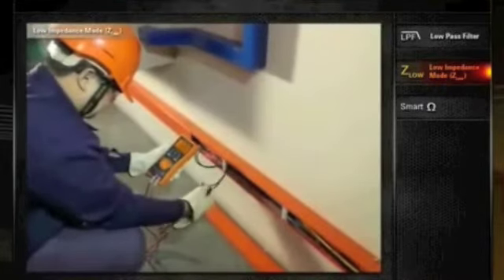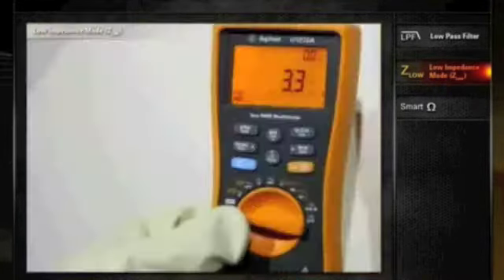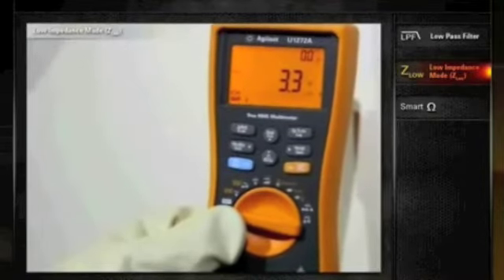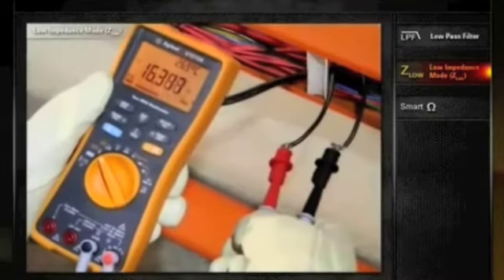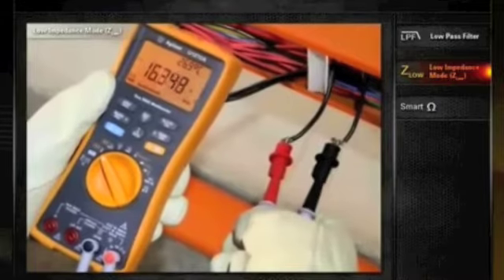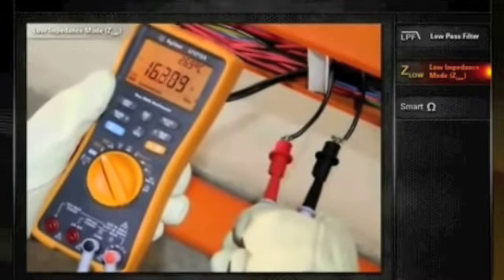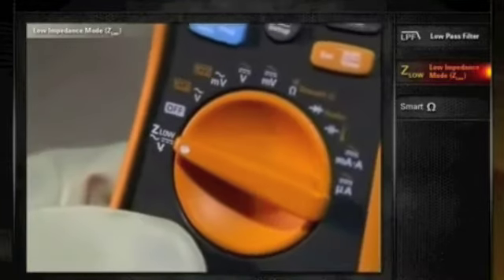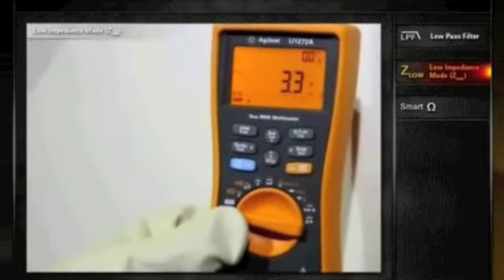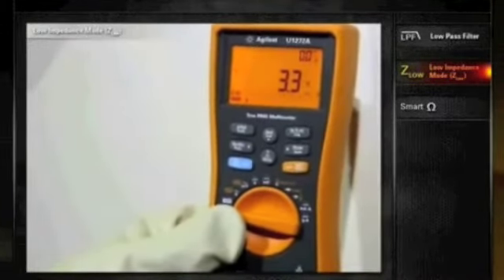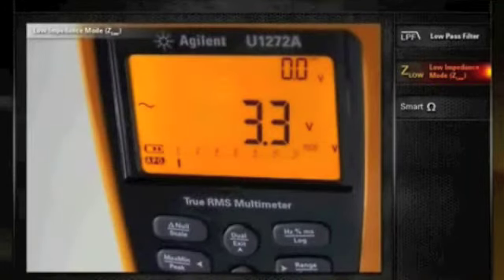The Agilent U1270A is a dual impedance handheld digital multimeter and offers both high and low input impedance modes. The low impedance mode or Z-Low will eliminate false stray voltage readings in non-energized wiring. The DMM now shows the accurate voltage measurement.